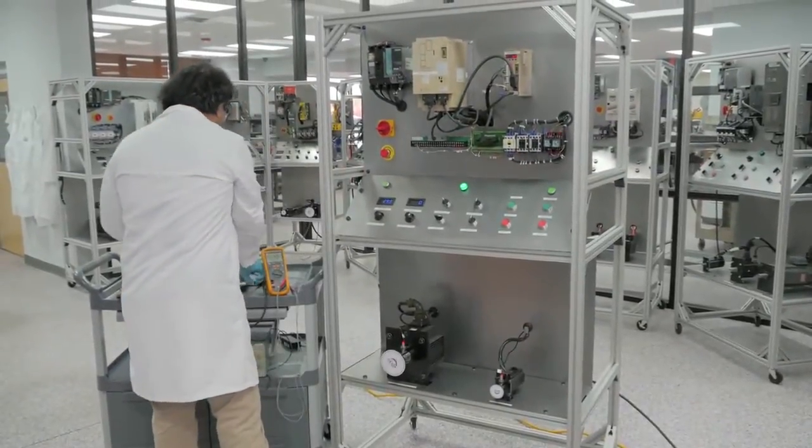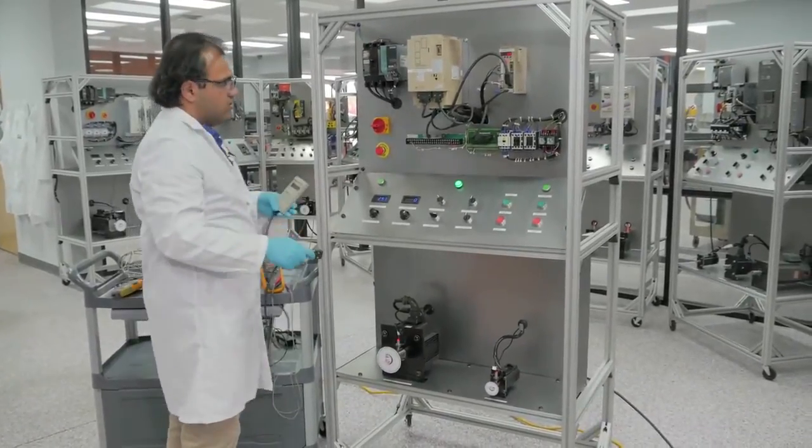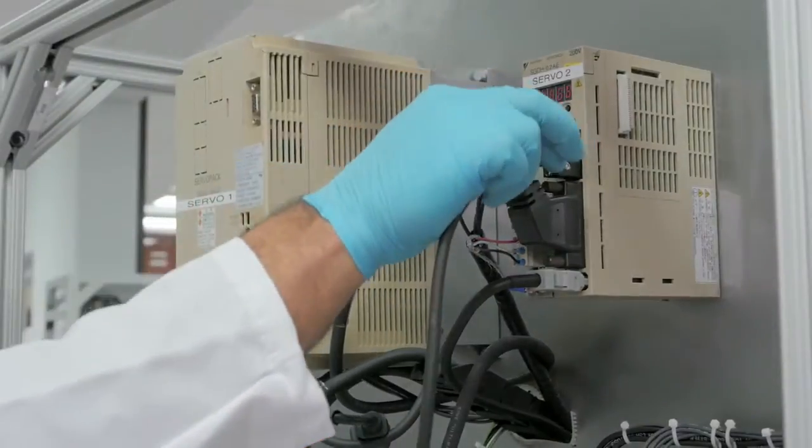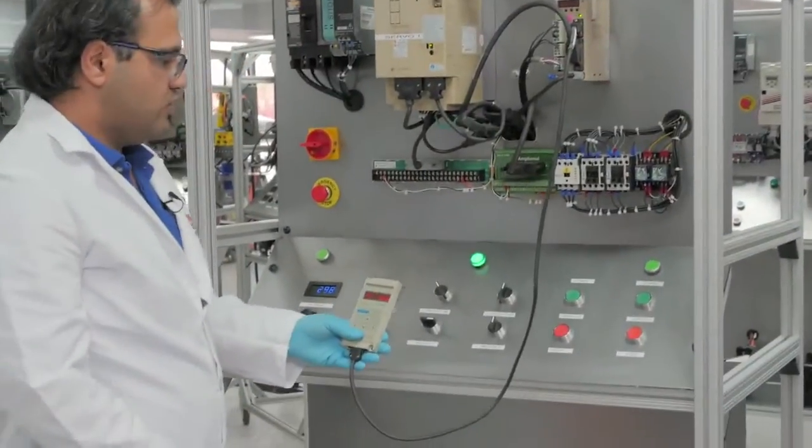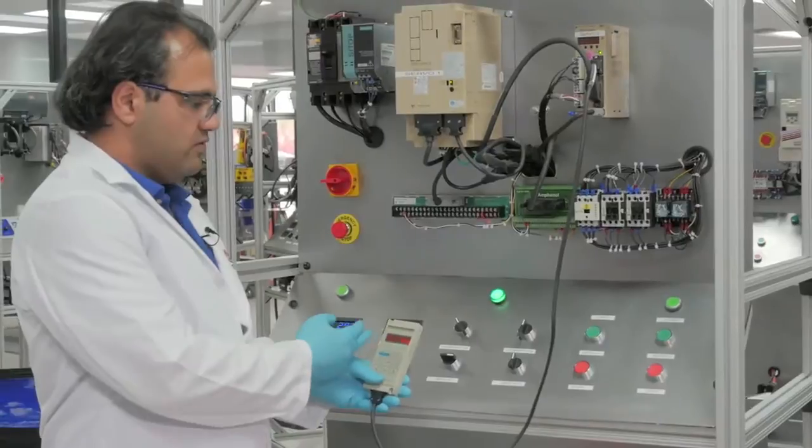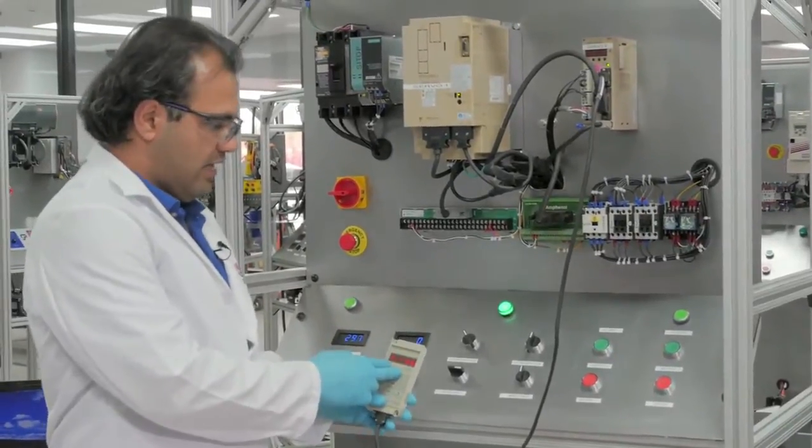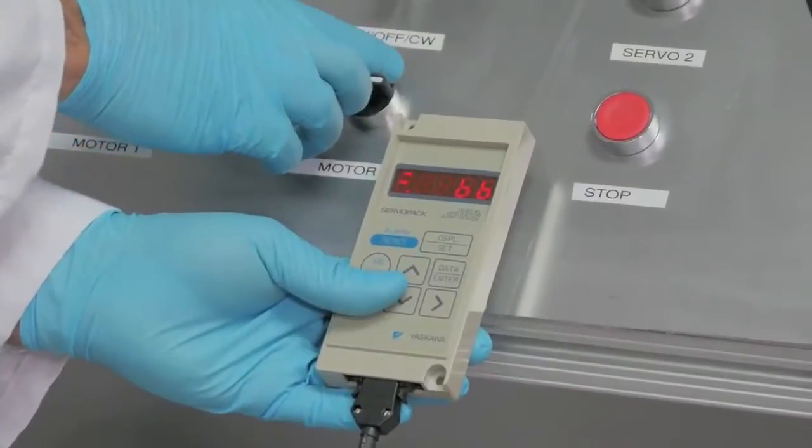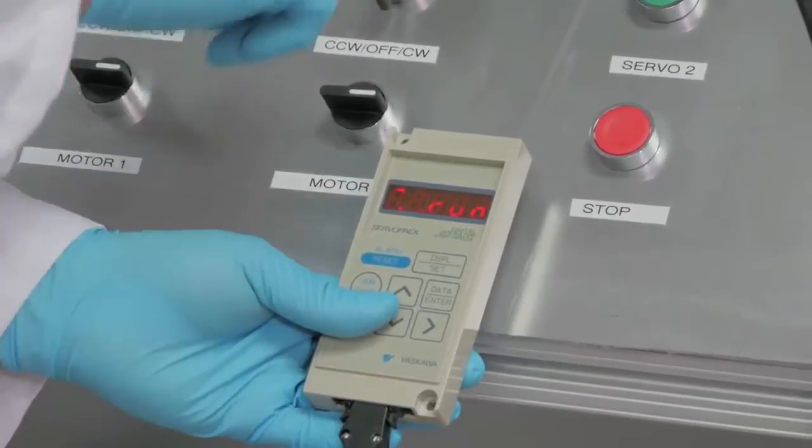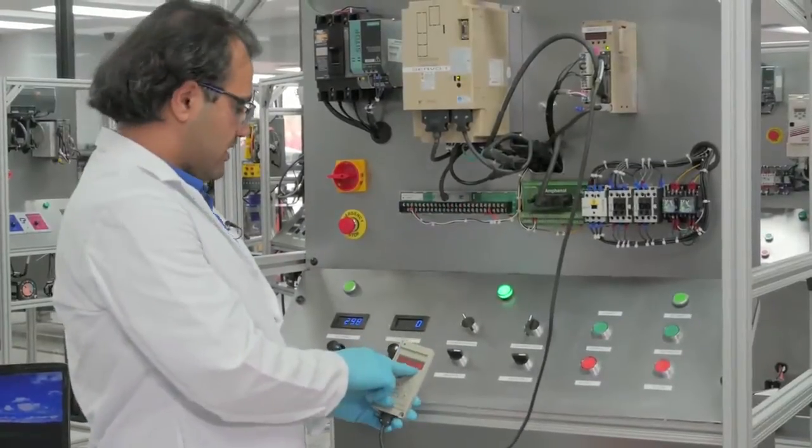And we have another control panel for these units SGDH series. As you see we don't have any faults and the drive was ready for enabling. When we enable the drive it goes into run mode and waiting for the speed command.